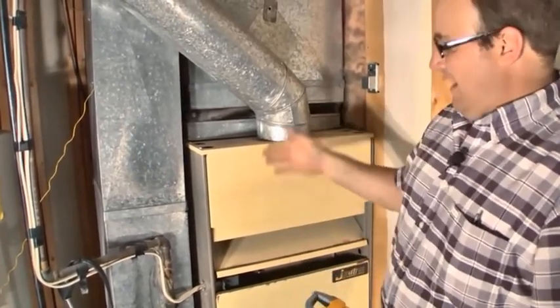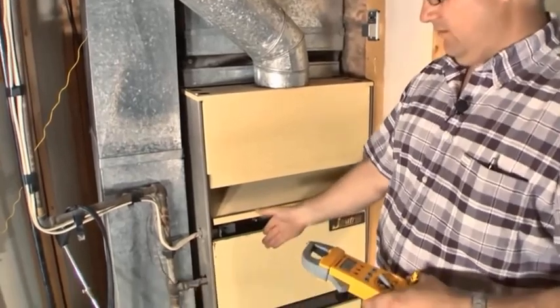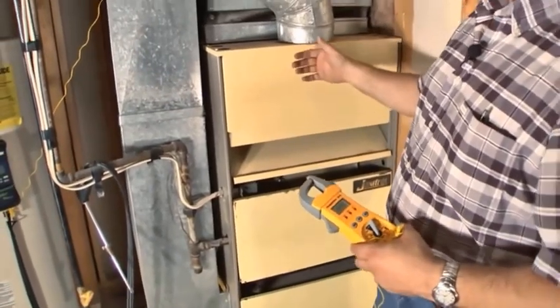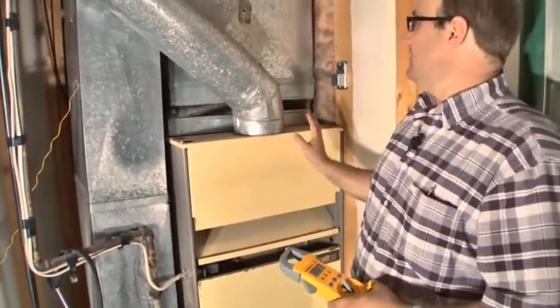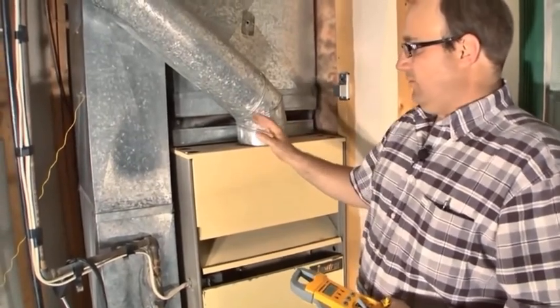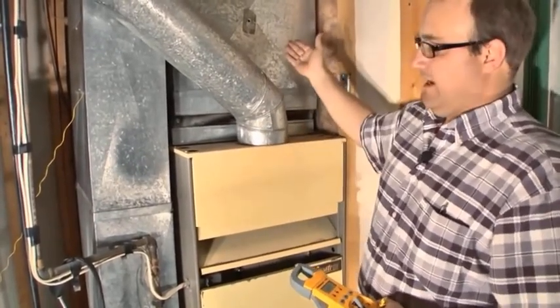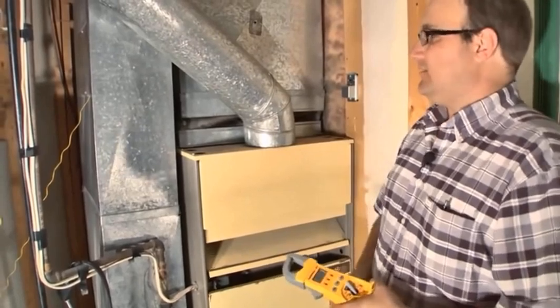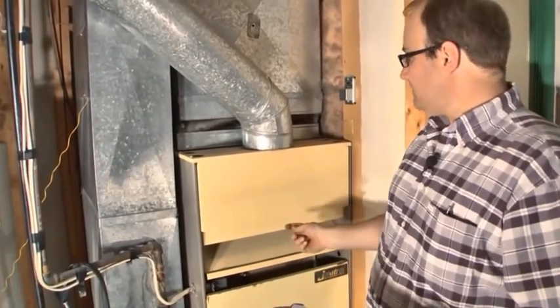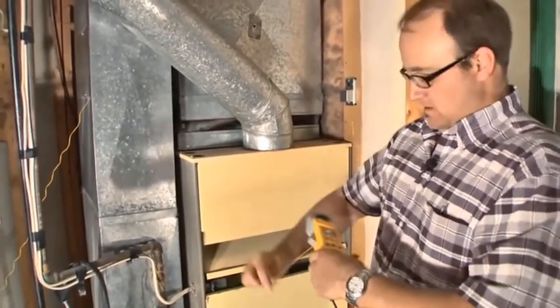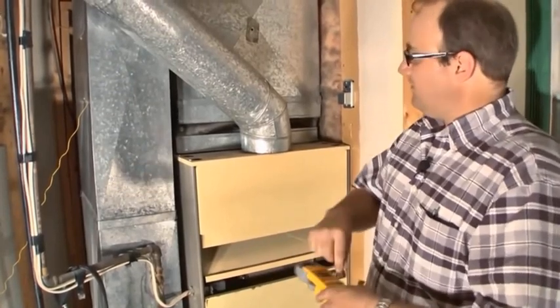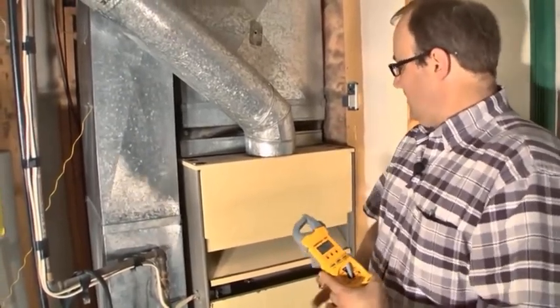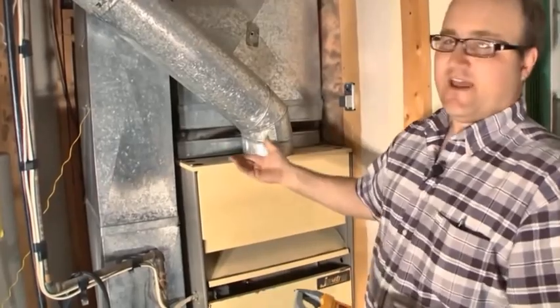So really, by changing this filter, we're going to be able to have a pretty good effect on the efficiency of this furnace when it's all said and done. We'll put a new filter in there, we'll get a new heat rise, and it'll drop dramatically, and this thing will run much more efficiently. So we've got a little work to do, change that filter, and then we'll get the fan off temperature at that point in time.